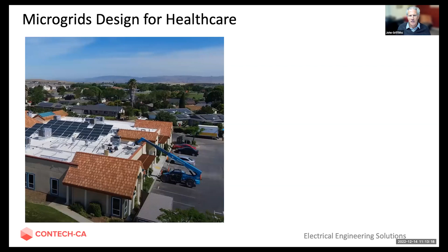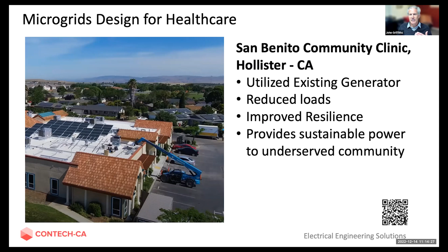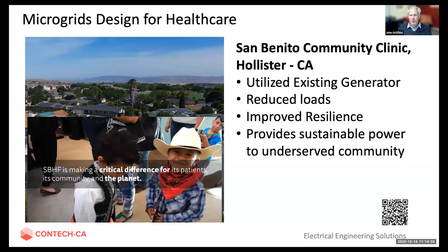This one is relevant to SNFs: the San Benito Community Clinic in Hollister, California. You can see in the picture on the left it originally was a community clinic, not high occupancy. Our approach was to go to the site, evaluate it, look at the loads. There was a relatively new generator, which we incorporated into a hybrid inverter, so we can use the generator when needed, if there's not enough from the batteries and solar. This improved resilience. The other important point is to look at reducing loads - we did LED retrofits and HVAC upgrades. That's an important step that shouldn't be overlooked, because as engineers we're happy to design a big system, but that's not what you want to pay for or operate - reduce the loads first. I'm particularly proud of this project, providing sustainable, resilient power to what is a traditionally underserved community.